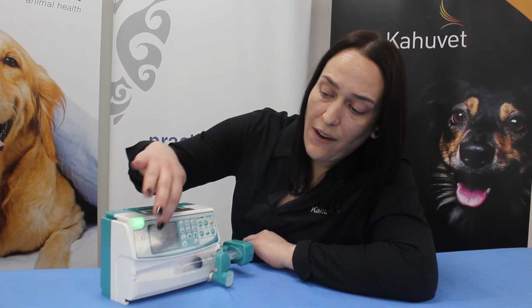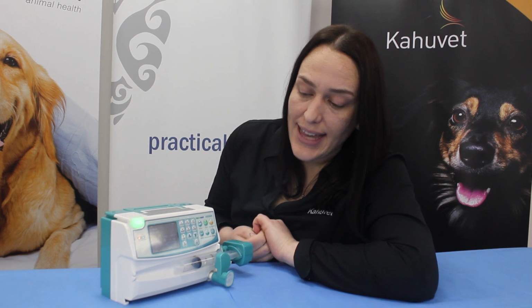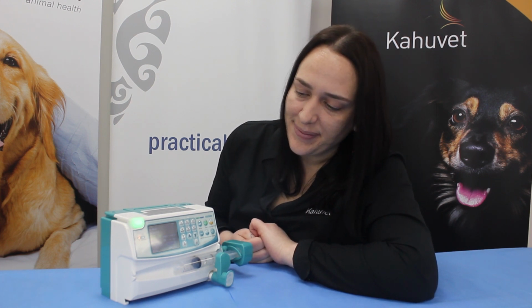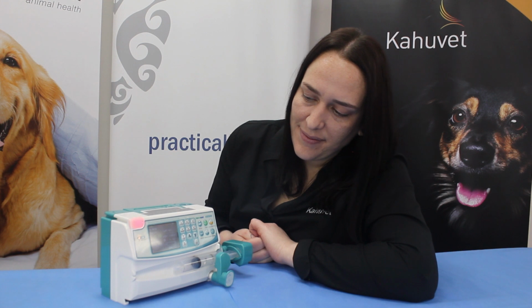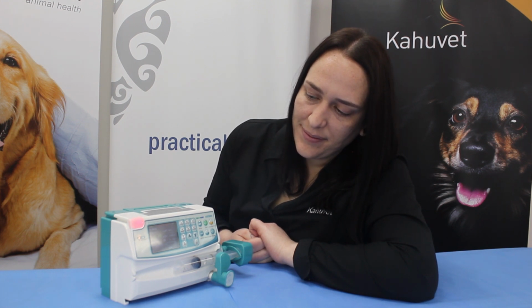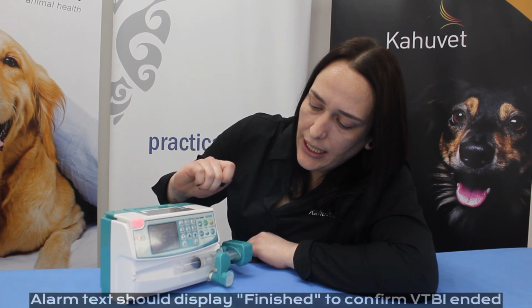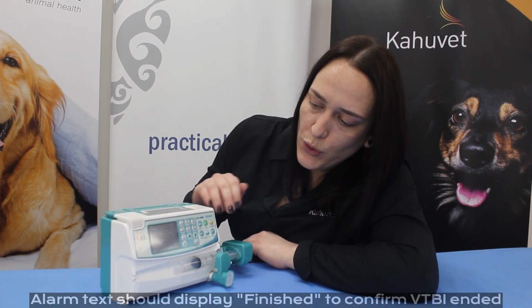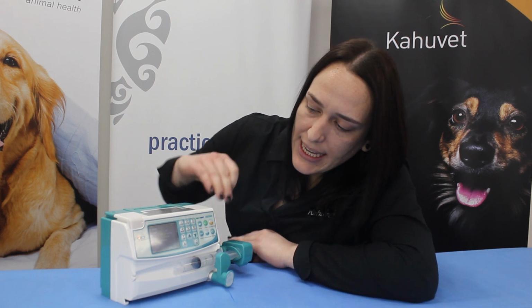We've just headed into our final mil of our infusion now, so we should see our syringe pump alarm shortly with a finish signal, and hopefully that line is accurate on our 10 mil mark. Awesome, so infusion's finished with our LED light and alarm signaling, so we can just press stop to go back into our hold screen. And we can see our syringe contents are nicely on that 10 ml mark. So this is showing that this pump here is delivering accurately.